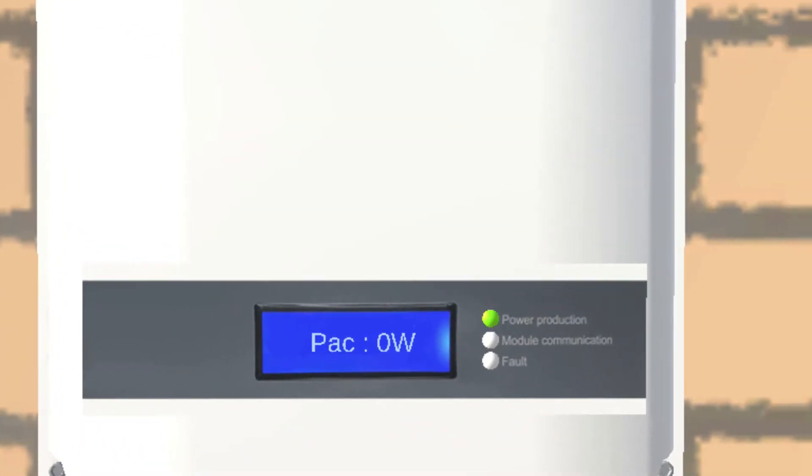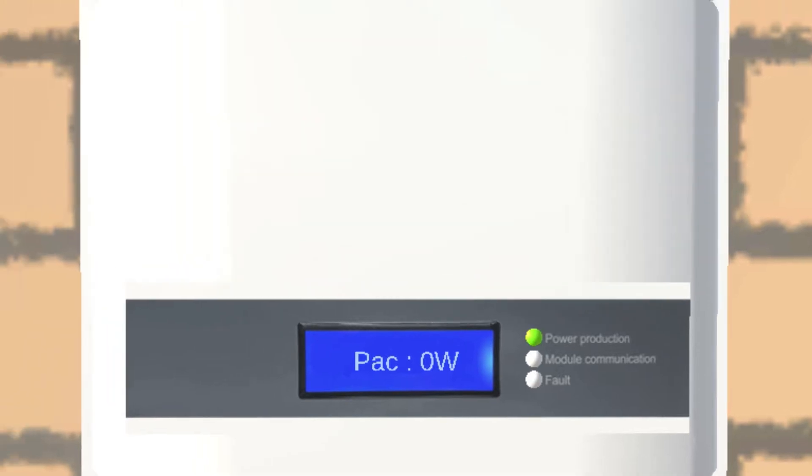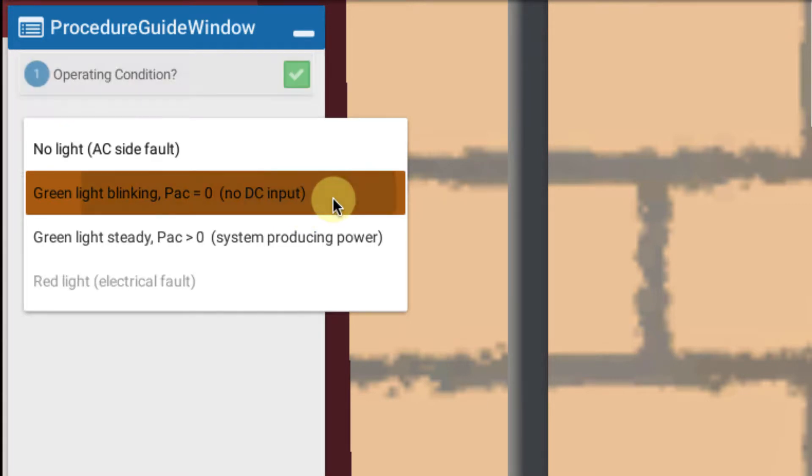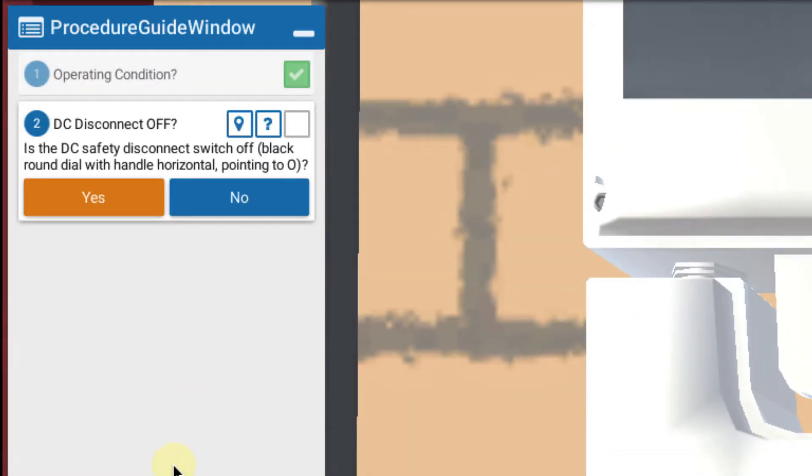In this case our case is the green light is blinking and the power AC is zero. So that indicates no DC input from the solar array. So we're going to click on that as our choice.